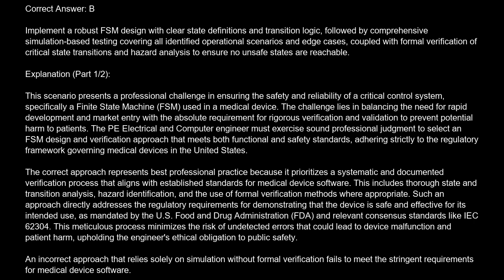This includes thorough state and transition analysis, hazard identification, and the use of formal verification methods where appropriate. Such an approach directly addresses the regulatory requirements for demonstrating that the device is safe and effective for its intended use, as mandated by the U.S. Food and Drug Administration, FDA, and relevant consensus standards like IEC 62304. This meticulous process minimizes the risk of undetected errors that could lead to device malfunction and patient harm, upholding the engineer's ethical obligation to public safety.